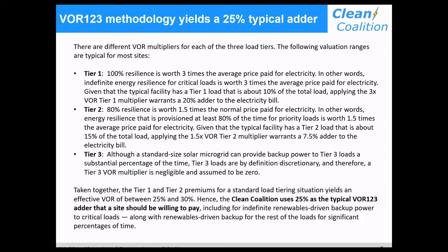The 1, 2, 3 is by tiering the loads. We asserted that the tier 1 loads, if you're going to keep them on 100% of the time, are worth about 3 times the average price paid for electricity. Keeping the tier 2 loads on for at least 80% of the time is worth 1.5 times the normal price paid for electricity. Then the tier 3 loads are discretionary - most people are not going to pay anything more for keeping the tier 3 loads on, so there's no multiplier effect on tier 3.